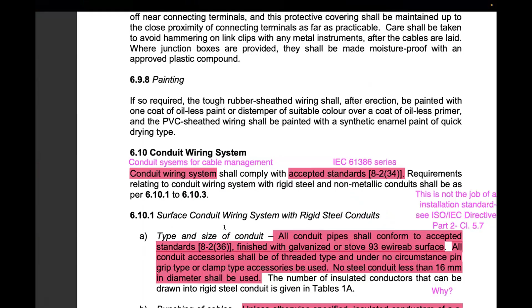So this is table 1A. You see this particular section talks about conduit wiring systems. When it comes to table 1A, you see this is talking about the maximum permissible number of single core cables up to and including 1000 volts that can be drawn into rigid steel conduit. The concern I have with this table is that it has taken a certain standard size of cable and a certain external diameter, and it has done these calculations.